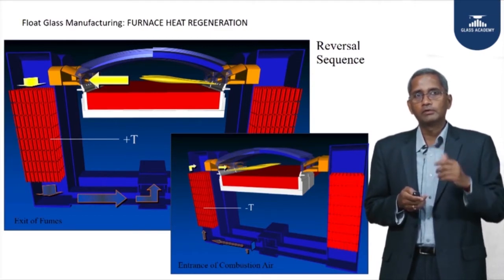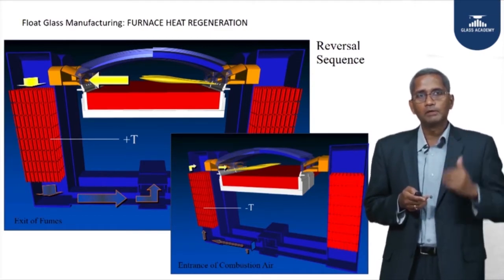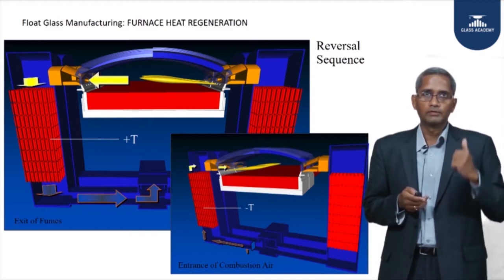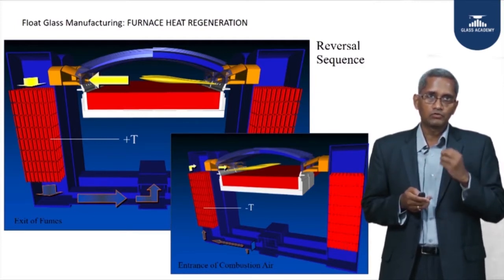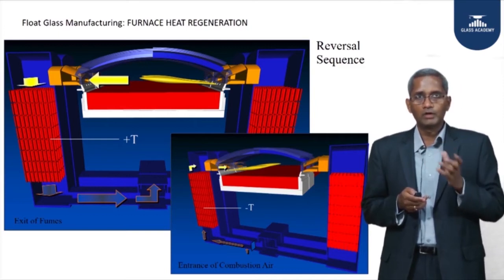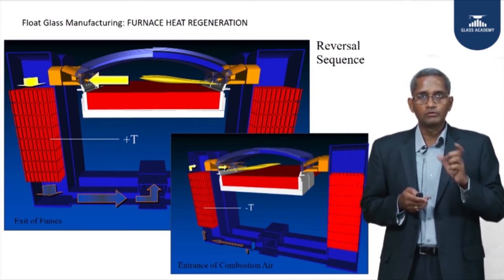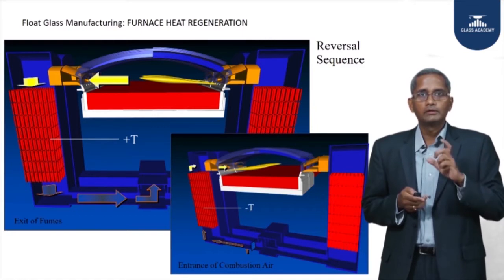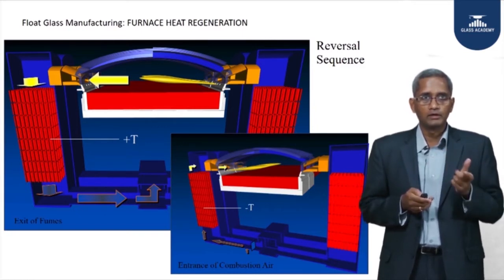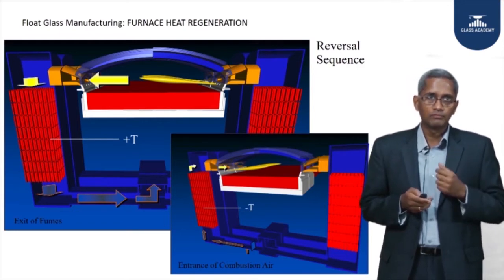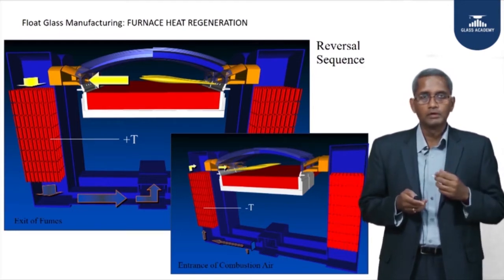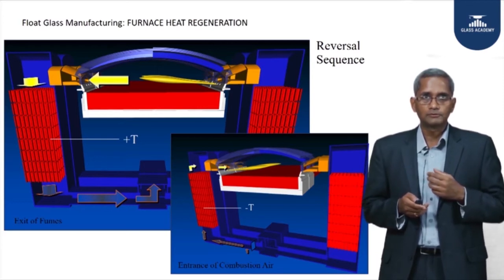This preheated combustion air reacts with fresh fuel to keep the furnace temperature at 1600°C. During this 20-minute period, with firing from the left hand side, the flue gas goes to the right hand side regenerator, which now starts to absorb heat. Every 20 minutes we swap — called a reversal — and the heat is recuperated back into the furnace. This type of furnace is called a regenerative furnace, which is quite normal among all glass manufacturers.